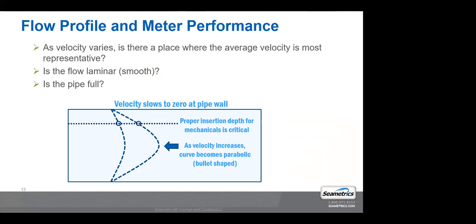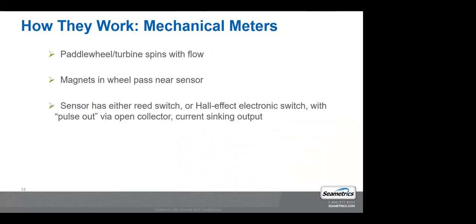Typically, flow meters require a full pipe of water as well to perform correctly. So mechanical meters, how do they work? They're pretty simple. There's either a paddle wheel or a turbine that spins as the water's flowing through the line.